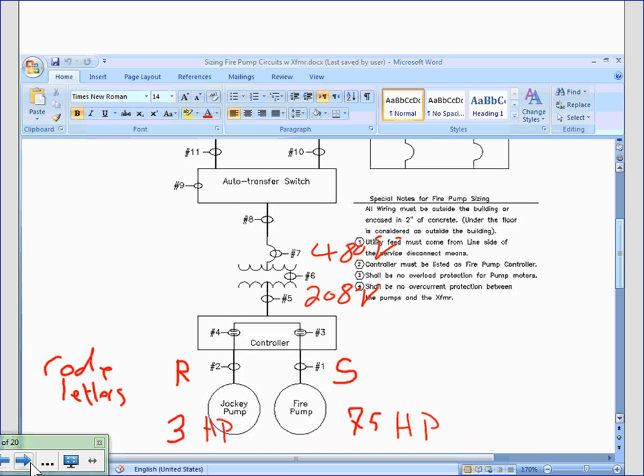The second one, guys, is now we have a transformer. I injected a transformer right between the auto transfer switch and the jockey pump because I want to run them on a 208 system, and my system coming to my building is 480. You guys did an example for me, homework. That was a homework example. 480, 208. Same thing. To solve the problem, I need the primary and the secondary of the transformer. I need the horsepower for the two pumps, and I need the code letter for both of them.